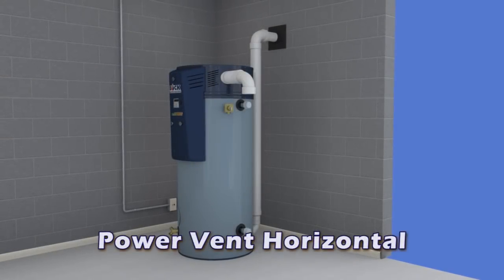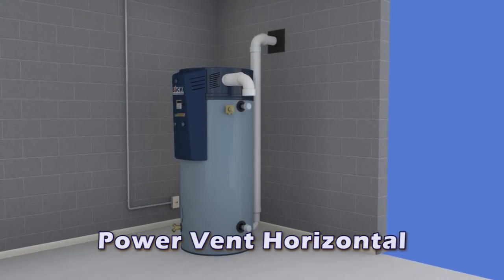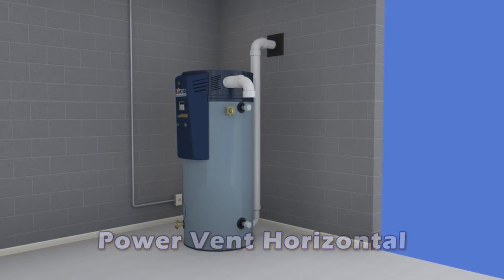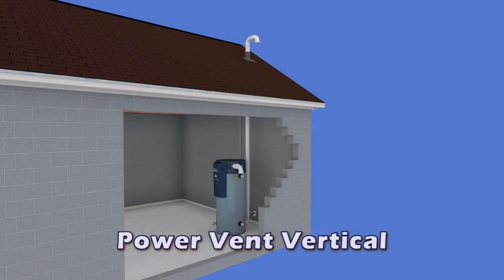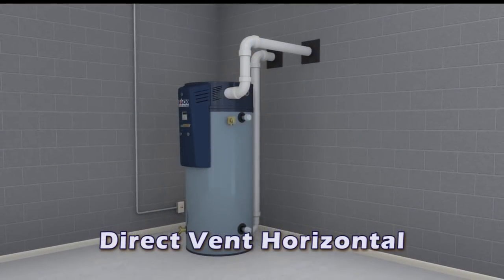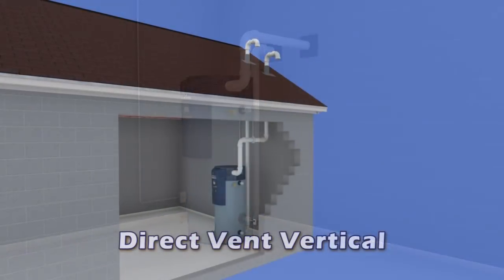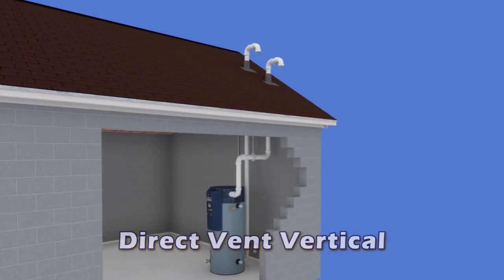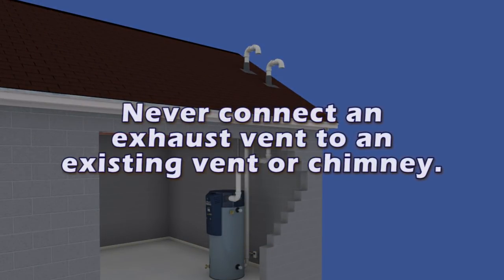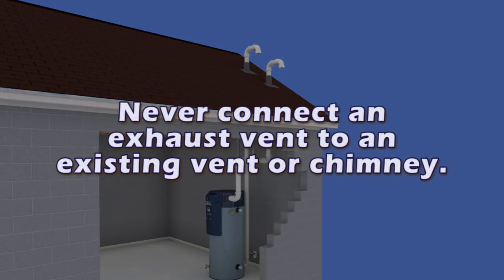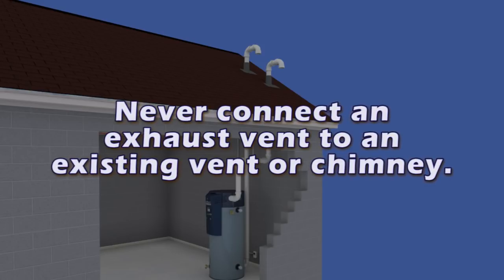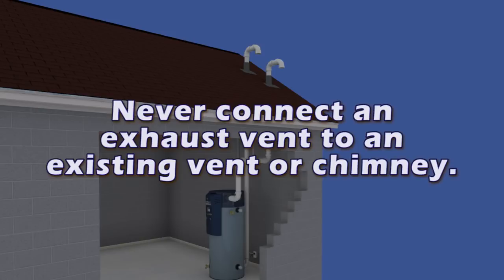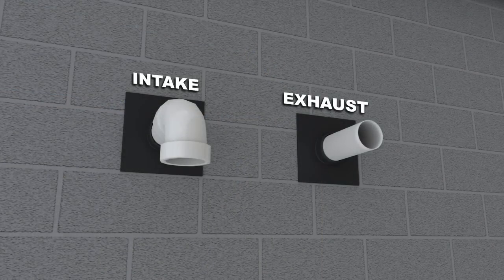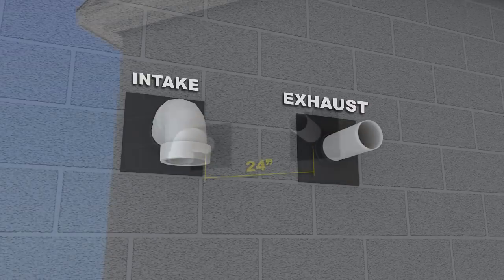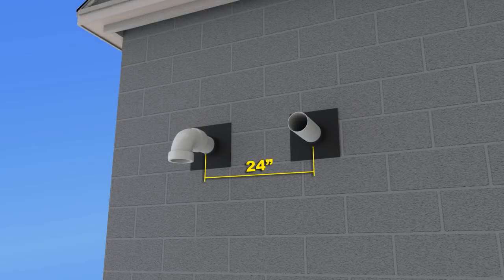The optiTHERM modulating gas water heater can be vented and terminated in the power vent horizontal configuration, the power vent vertical configuration, the direct vent horizontal configuration, and the direct vent vertical configuration. Never connect the exhaust vent to an existing vent or chimney. Refer to the manual for approved methods. All clearances for terminations must comply with local codes. The air intake must never be installed above the exhaust termination, and there must be a minimum of 24 inches between the inlet and exhaust terminations.